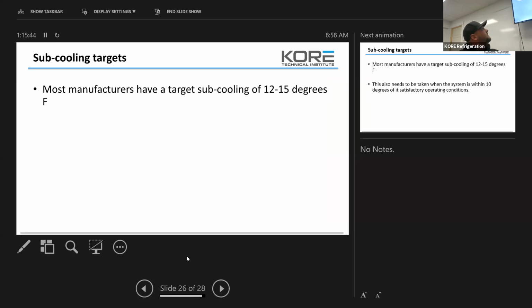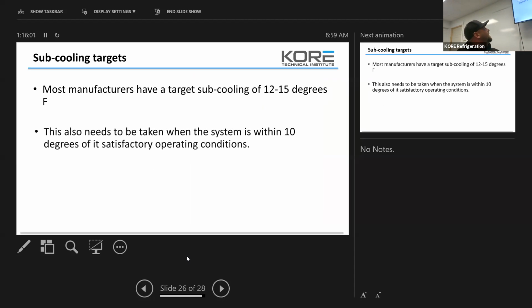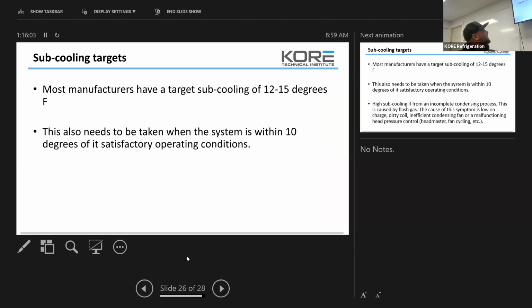Subcooling targets. Most manufacturers have targeted a subcooling of 12 to 15 degrees. Again, consult the OEM. Google it. Talk to them. It may be different. I'm just trying to hit the range of where we see it most of the time to give you guys a starting point. Readings also need to be taken when the system is within 10 degrees of satisfactory operating conditions.